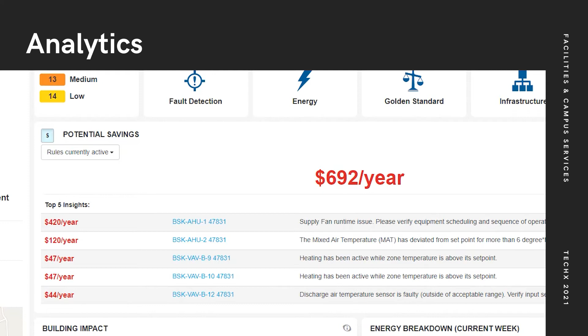If we look at the building automation system summary information screen for the VAVs, we see that the supply temperature, also called discharge temperature, is reading minus 97.5, which obviously indicates an issue with the sensor or wiring.